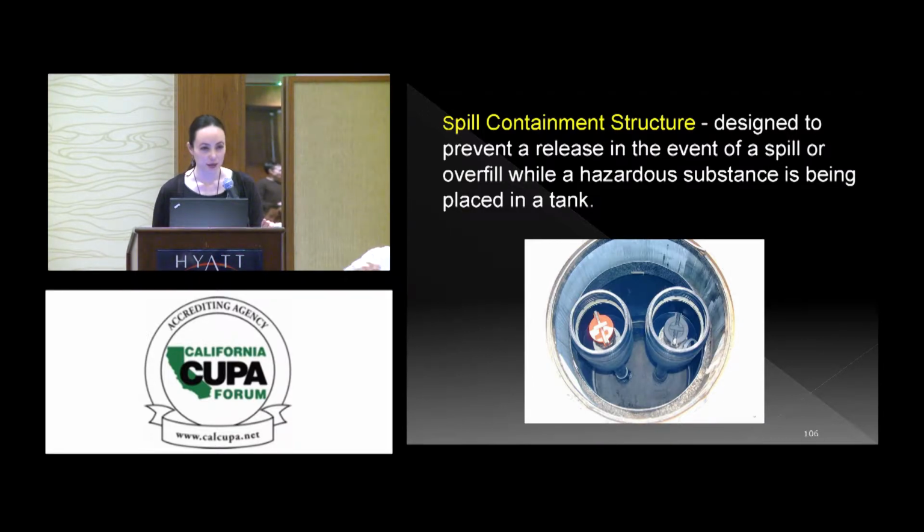Is a spill bucket required there? Yes, it is required, and the reason is that spills or vapors can also exit from that port, from the vaporizer, and they can also condense and create liquid. So we need something to capture that liquid. That will be on the vapor bucket.